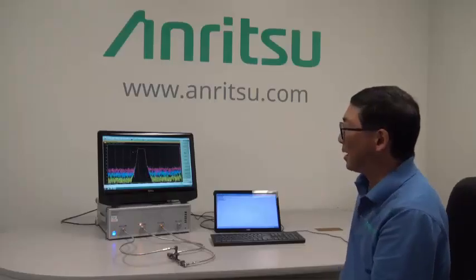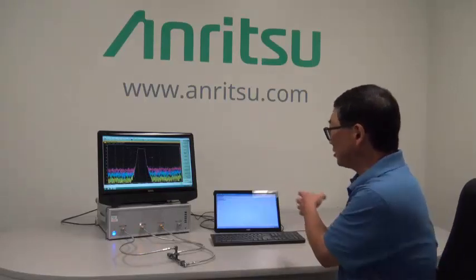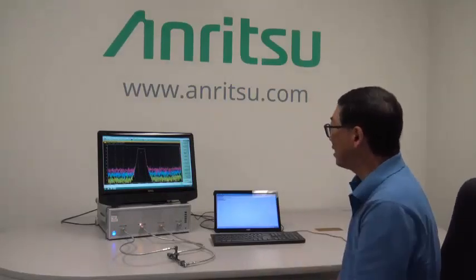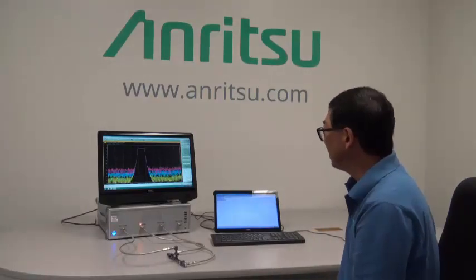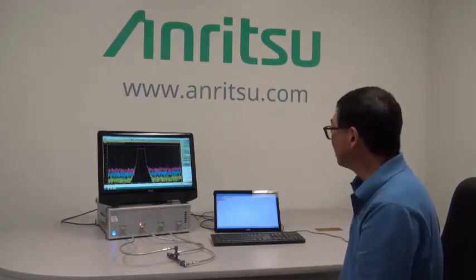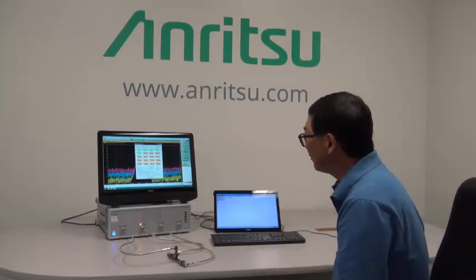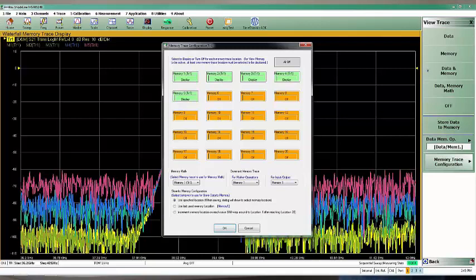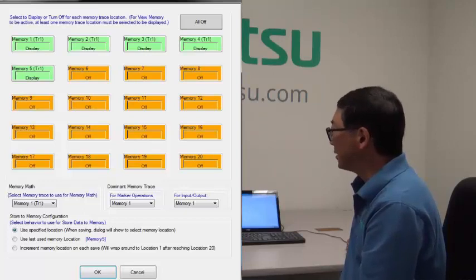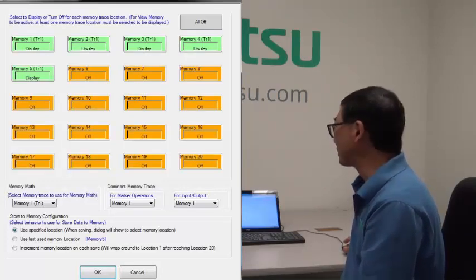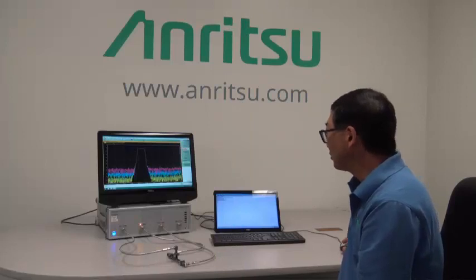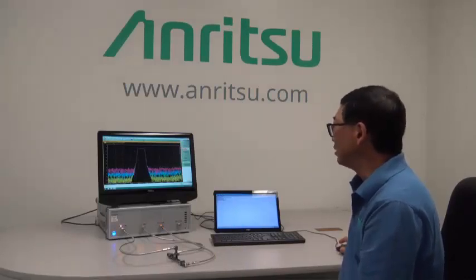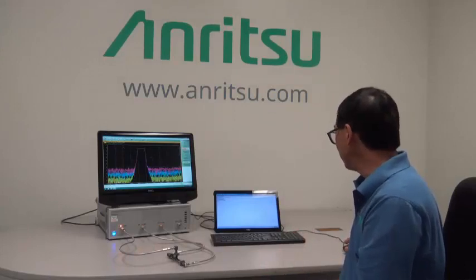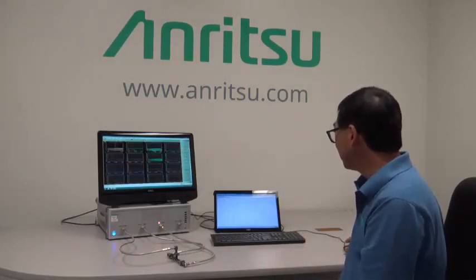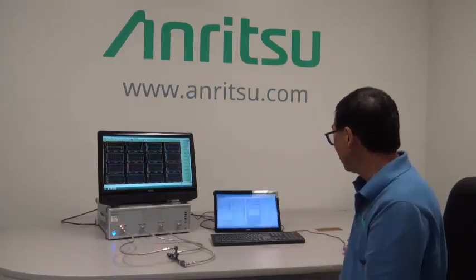One unique thing about the ShockLine software, in addition to running it off of this script file, is that you have the ability to interact with the GUI as well. So we can go in and look at the display and see in our memory configuration menu that we've stored the 5 IF captures into the first 5 memory spaces of the 20 that are available. You can go through the rest of this, interact with the GUI, and go back through and run the rest of this easyTest script, which then finishes out and quits out.